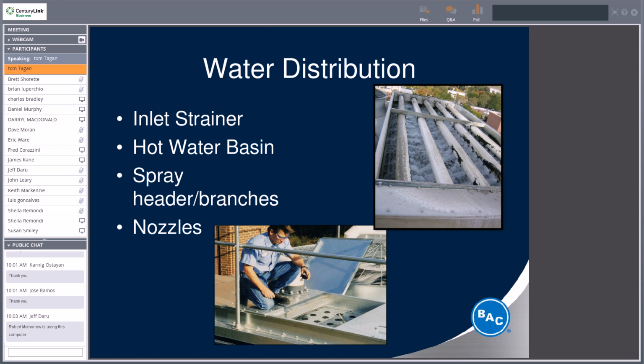So that was the 17 pages or so of 27 pages or so of the O&M manual. That was specific to the Series 3000 that I wanted to use as a guide. Again, take us up on our inspections. If you have a different style cooling tower, a closed circuit cooling tower that you're concerned with, or you've just recently taken over the building and you're not quite sure how it operates, let us know. We'll come out, explain the function of the tower, take a look at some of the components, and again, make recommendations on what should be replaced and what shouldn't.